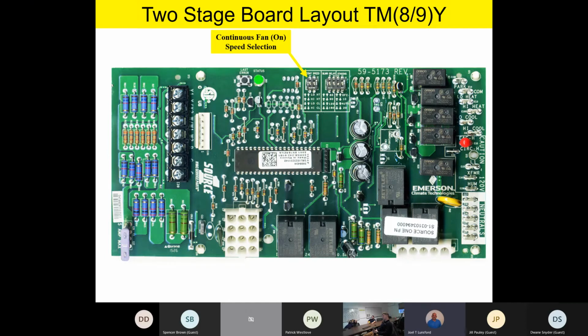Now remember, if you have a call for cooling or a call for heating, the board will override that. So this is strictly a continuous fan speed if there's no call on the board at all, except when the homeowner goes to the fan on position from auto to on on the sub-base assembly. So this is continuous fan speed operation that gives you some options other than just on or off.